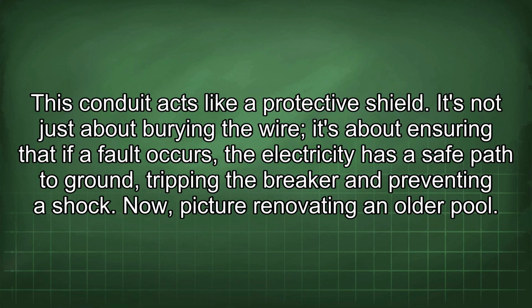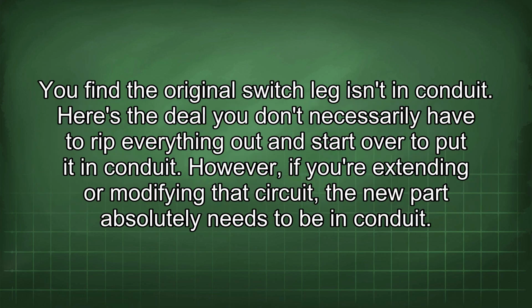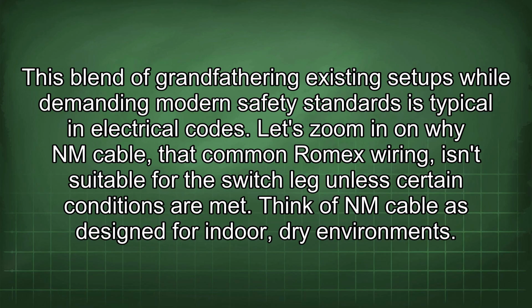Now picture renovating an older pool. You find the original switch leg isn't in conduit. Here's the deal: you don't necessarily have to rip everything out and start over to put it in conduit. However, if you're extending or modifying that circuit, the new part absolutely needs to be in conduit. This blend of grandfathering existing setups while demanding modern safety standards is typical in electrical codes.